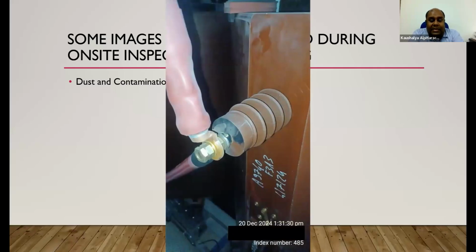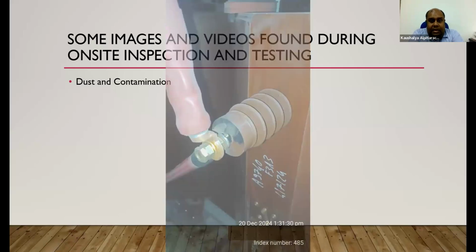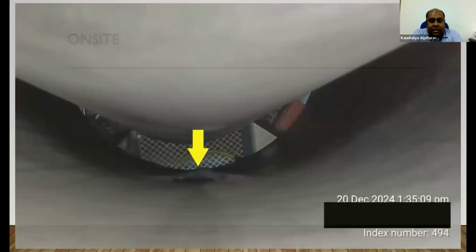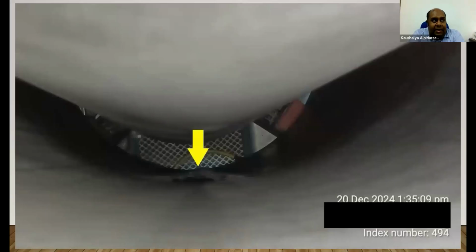Here you can see a flashover of a previous incident. A damaged LV winding of a transformer. This is of course a dry type transformer, a cast resin transformer. This was employed in a high surge generating and high harmonic area. This transformer was replaced three times. See what's the cost.